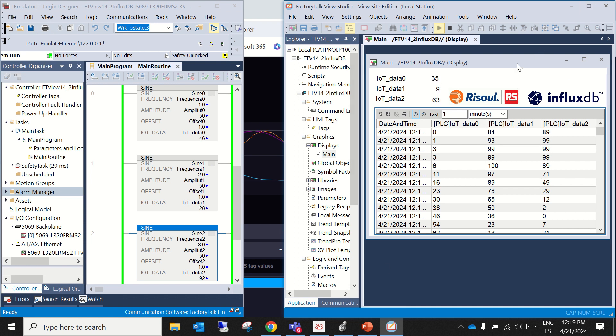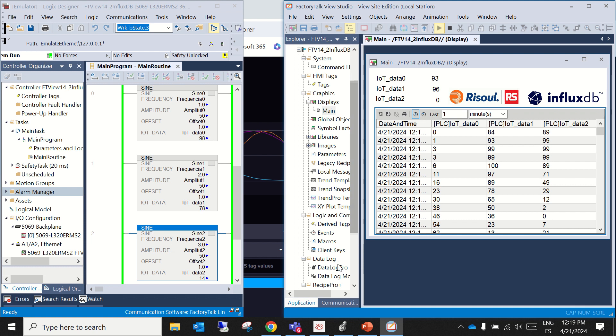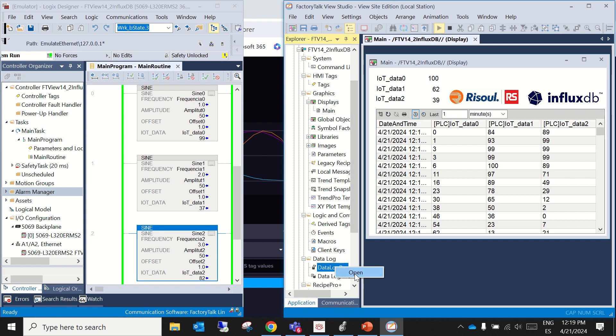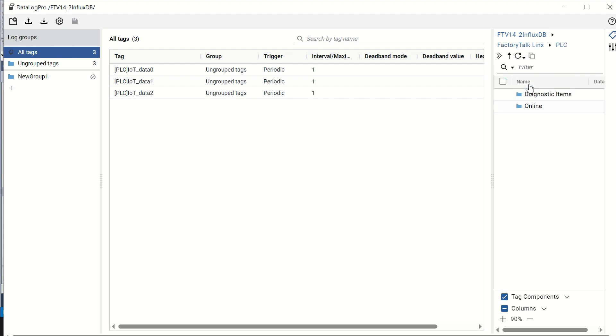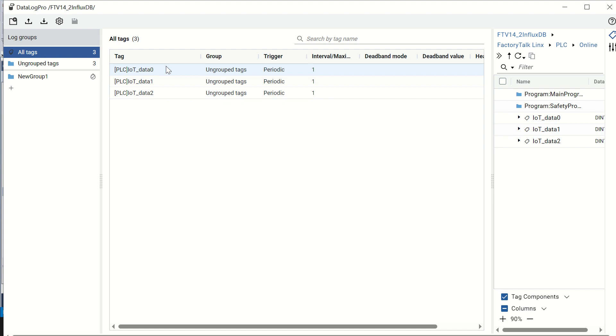If you need to log some variables, you use the DataLog Pro. You open the DataLog Pro, navigate through your FactoryTalk Linx communication driver, locate the tags, and click Add to populate the collection of variables that will be injected into the database.